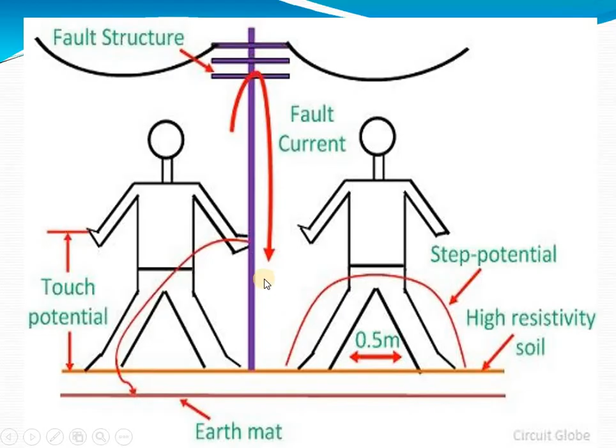There are ways to mitigate step and touch potential. The first method is reducing the resistance to ground of the grounding system. For example, if the fault current for a high voltage tower is 5000 amperes and the resistance to ground of the grounding system is 10 ohms, the ground potential rise, I fault into RTG, is 5000 into 10 equals 50,000 volts. If we reduce the resistance to ground down to 5 ohms and the fault current increases to 7000 amperes as a result, the ground potential rise becomes 7000 into 5, that is 35,000 volts, so the potential voltage is reduced. Thus, reducing the resistance to ground allows more current to flow into the earth at the site of the fault.